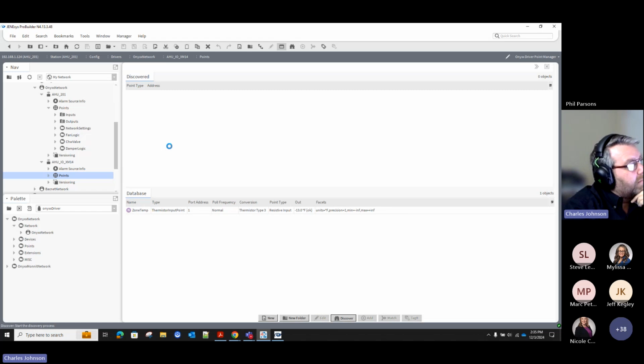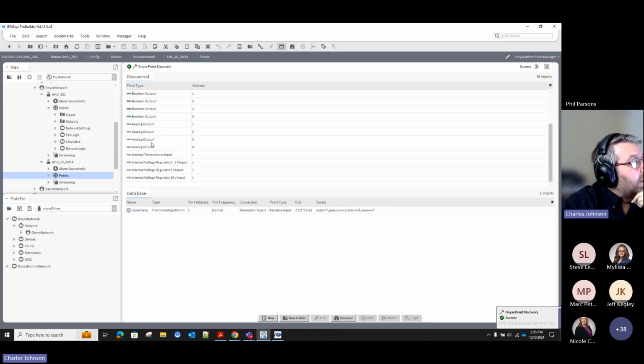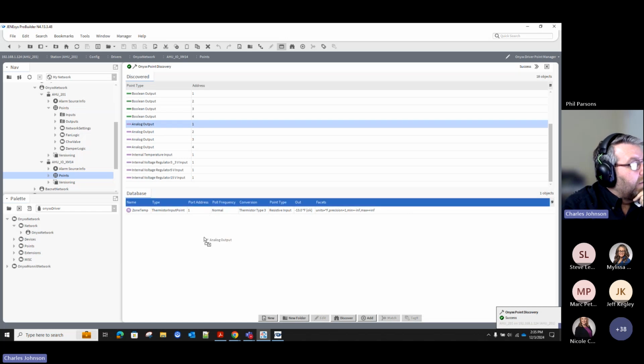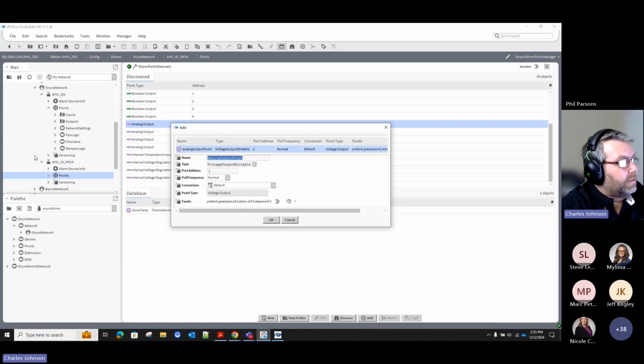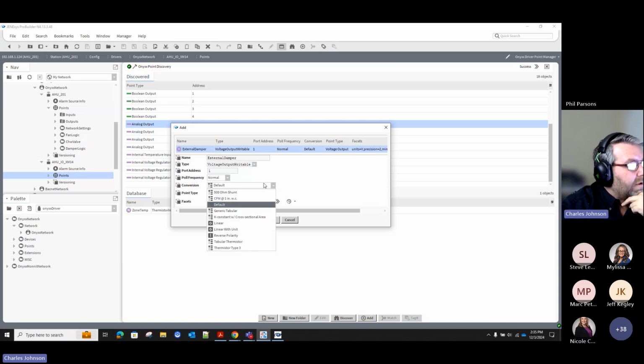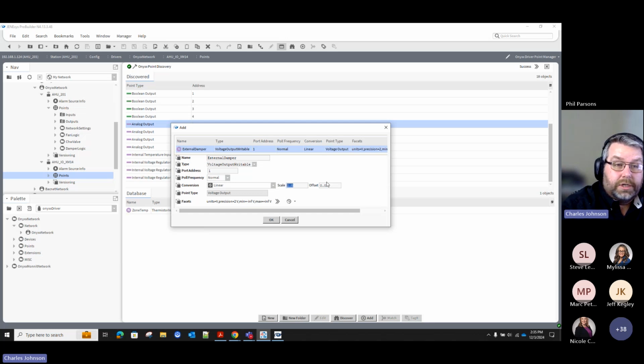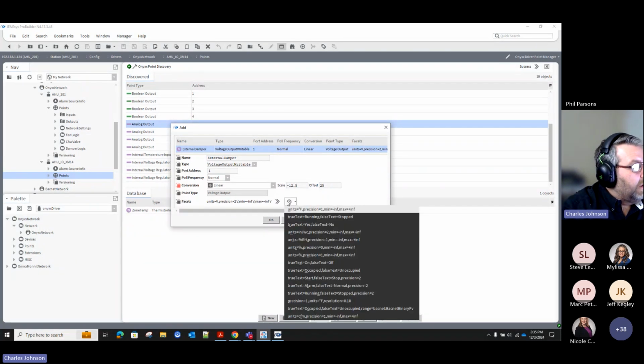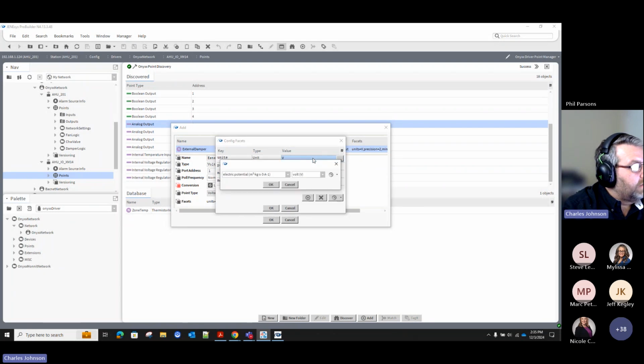And so as I go in again, I'll go ahead and bring in an analog output here, and I'll just name this external damper. As a conversion, it would just read voltage automatically. However, if you need to do a linear calculation, you would have to choose the scale and offset, much like you would do in your other I/O. So let's say this is going to be a 2 to 10, so we'll do 12.5, and then we'll do an offset of 25 here, and we'll set this as voltage.